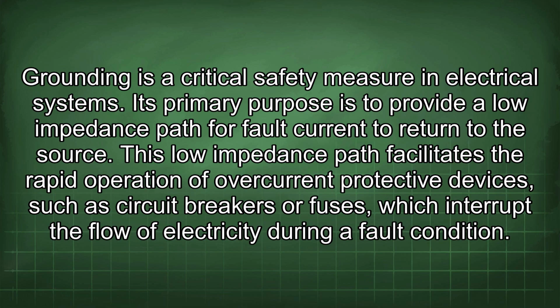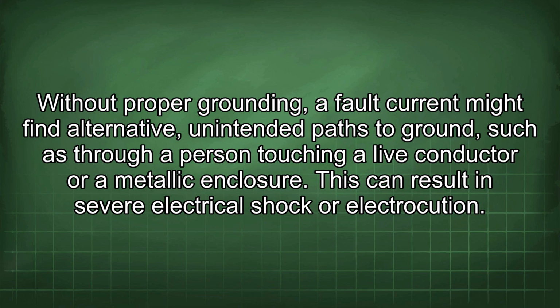Grounding is a critical safety measure in electrical systems. Its primary purpose is to provide a low impedance path for fault current to return to the source. This low impedance path facilitates the rapid operation of overcurrent protective devices, such as circuit breakers or fuses, which interrupt the flow of electricity during a fault condition. Without proper grounding, a fault current might find alternative, unintended paths to ground, such as through a person touching a live conductor or a metallic enclosure. This can result in severe electrical shock or electrocution.